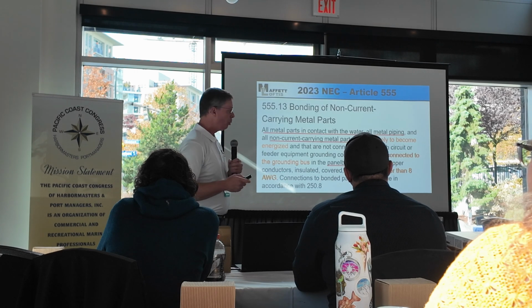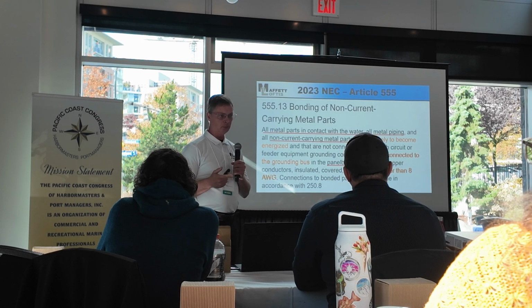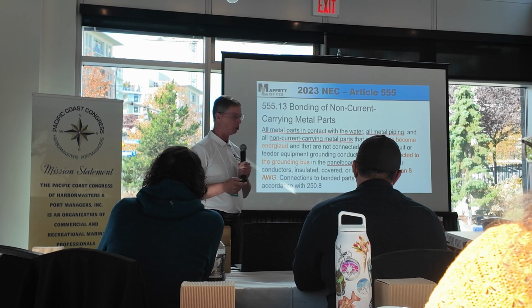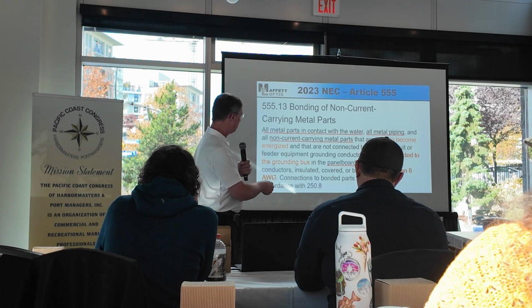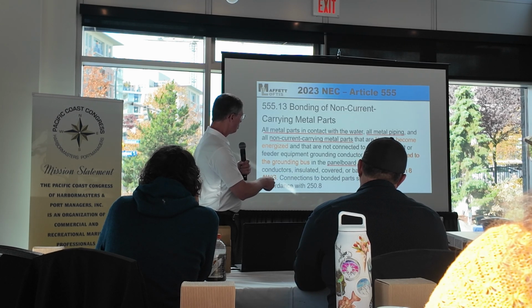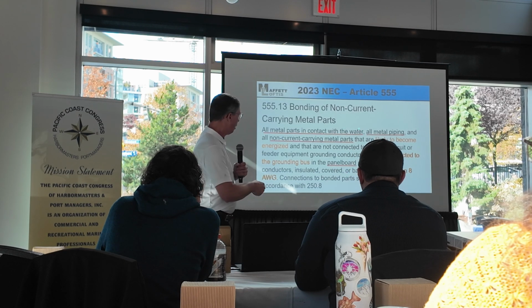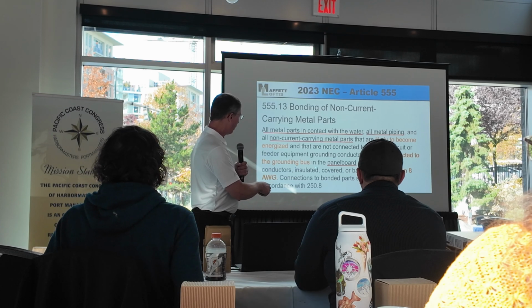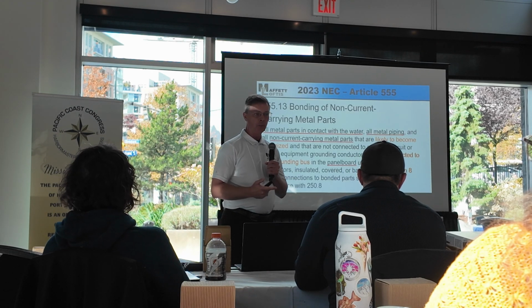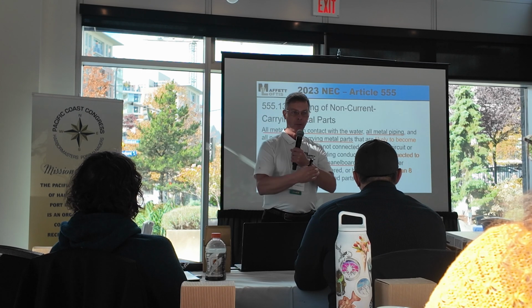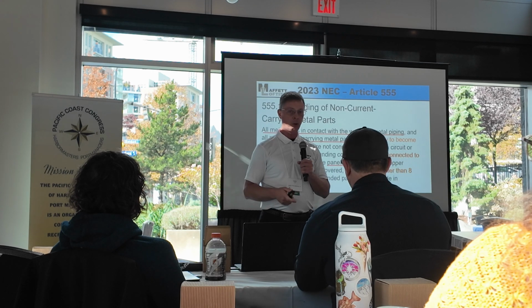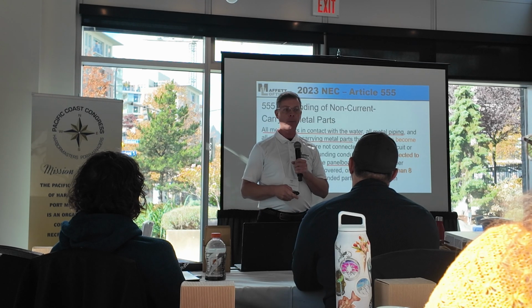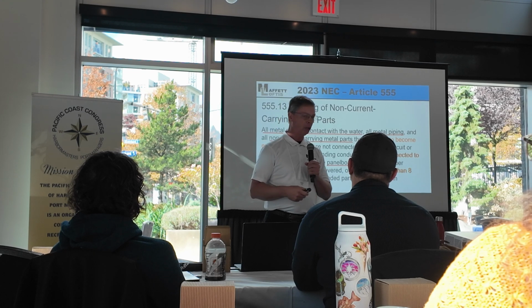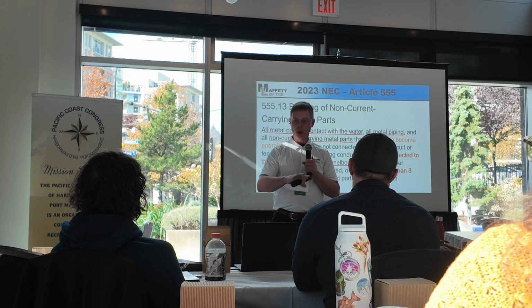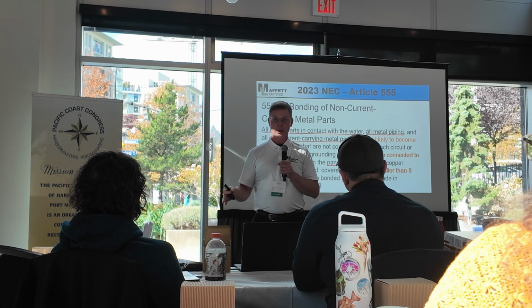Okay, so the issue is the intent was this, and it's some grammar, I think, through the code making panel, and they didn't do wordsmithing as well. But this likely to be energized has been interpreted as only applying to this last item. So what inspectors were doing, especially some in Florida, was saying that all metal parts in contact with the water shall be connected to the grounding bus using number 8 wire. Okay? And the issue is that if you had a timber dock and the cross bracing down at the bottom had through bolts, they were metal, they were in contact with the water, then every single through bolt was going to have to be bonded with number 8. Or if you have a concrete dock and you have some metal inserts or a metal plate somewhere that's nowhere even close to a piece of wire, it's going to have to be bonded. And that's actually happening right now in Florida.